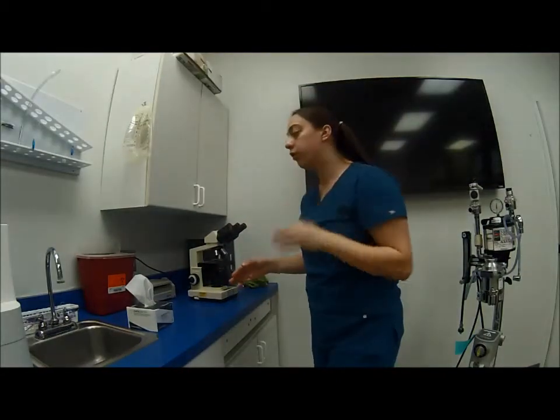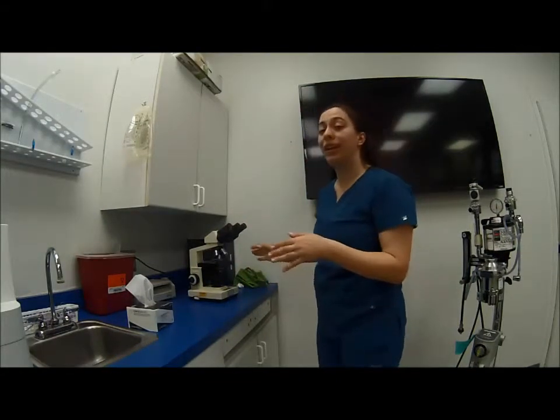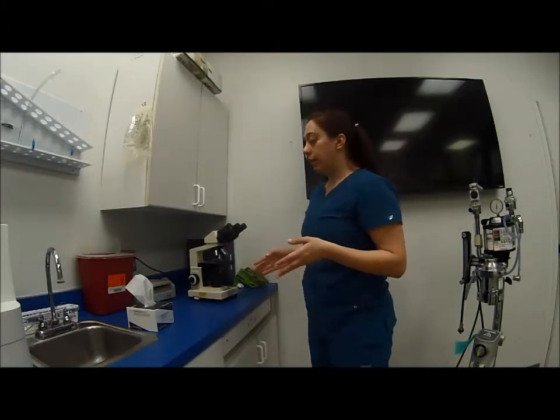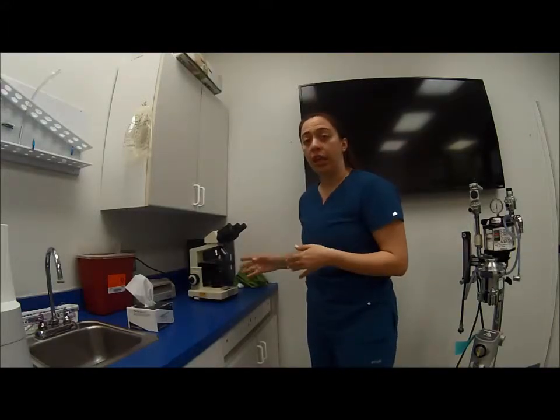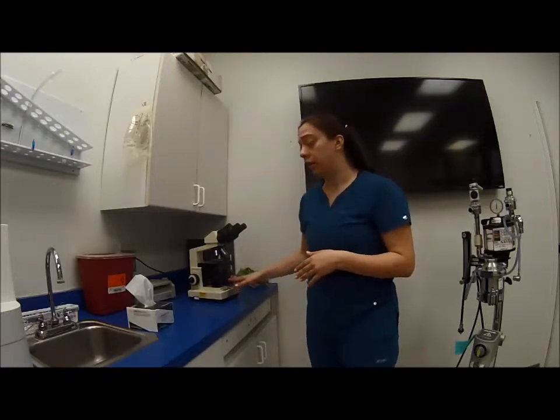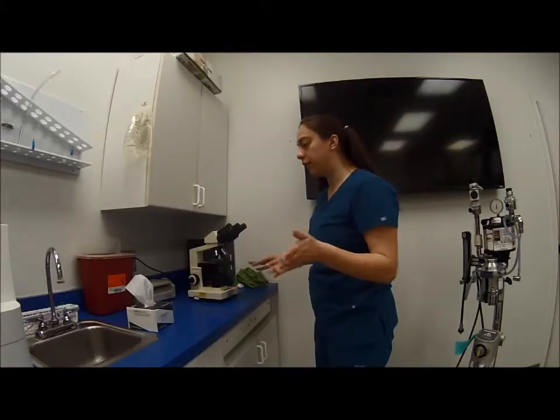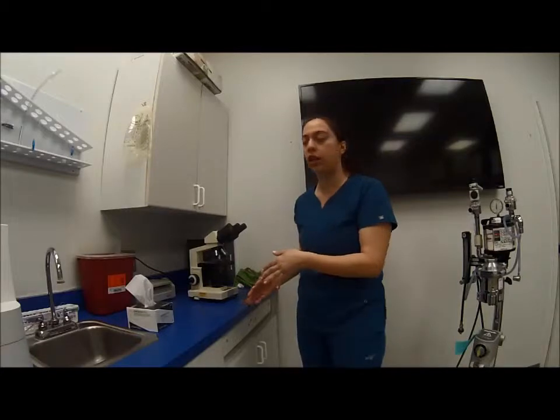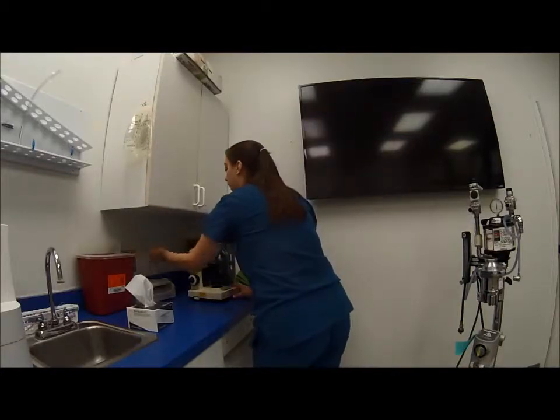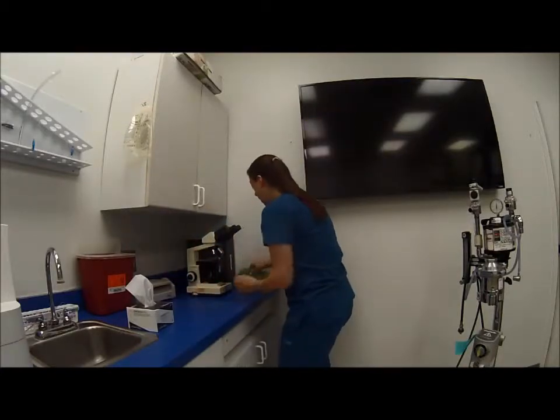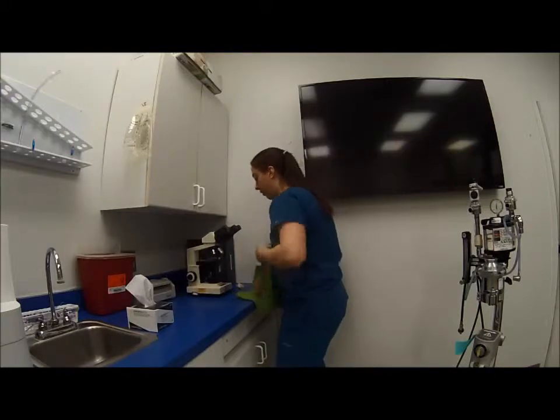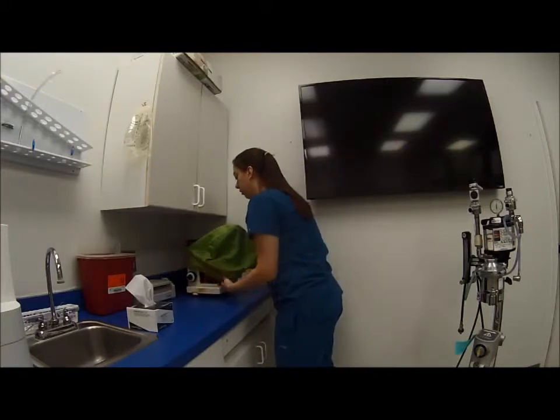It is also important to note to make sure you have your microscope in an area where it isn't going to be moved or jarred or shaken, because that can definitely damage this equipment, and to make sure it's someplace where fluids aren't going to be splashing, it's not going to get super dirty. So we have it here in this corner. I'm going to go ahead and put the cover back on since we're not using it.